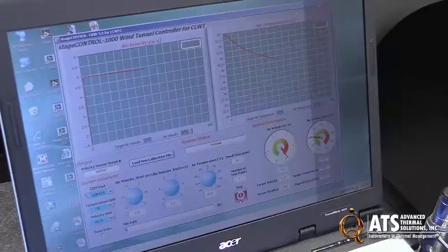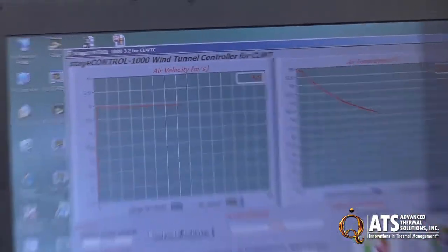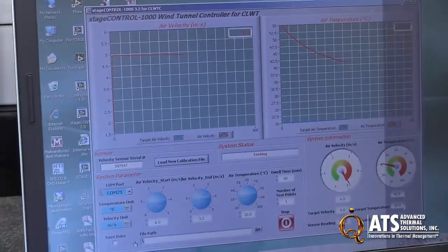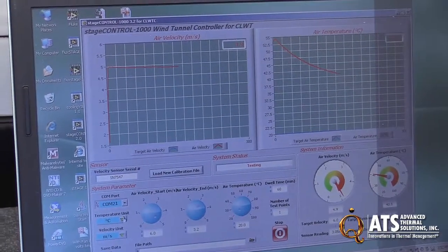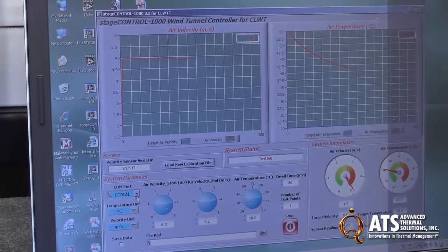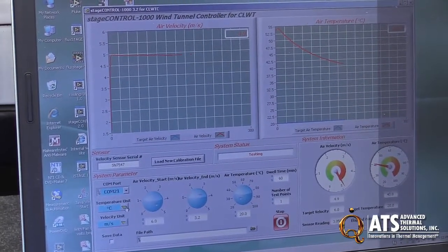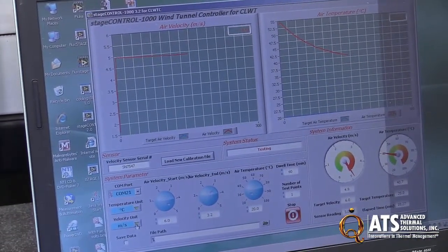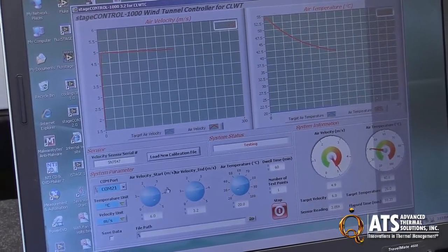The software is called stageCONTROL-1000, version 3.2, and has multiple inputs. First, when you connect the instrument to the computer, it has to automatically detect the COM port, which in this case is COM21. Then you can choose the unit for temperature—either degrees C or degrees F—and also the unit for velocity: meters per second or feet per minute.